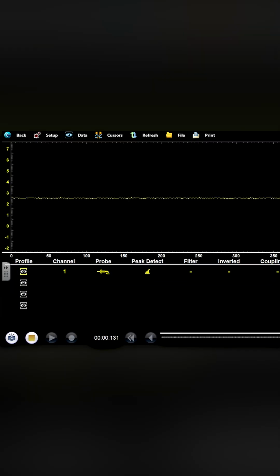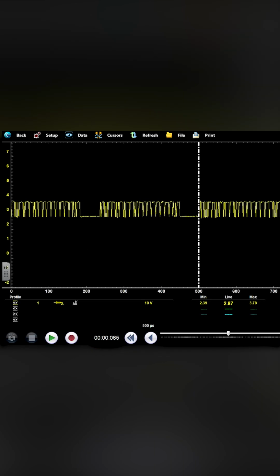The range is right for pin 6, 2.5 to 3.5, but it just has repeating patterns. We don't see CAN signals that look like that. Yeah, no, it's the same thing over and over, and there's no spikes at the beginning of the message. Yeah, that's wild.